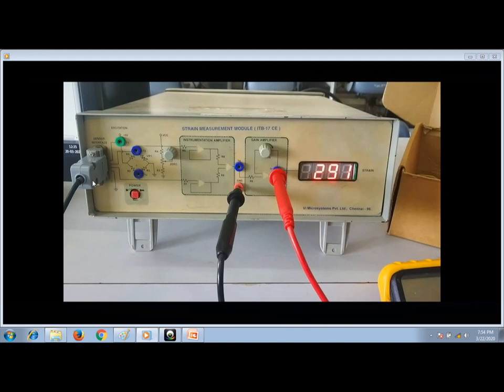The transducer is interfaced, you get the bridge output, and it is signal conditioned — that is, amplified. Across the multimeter terminals you get the electrical output in the range of 0 to 5 volts. The amplifiers are designed so that if strain is 0 you get 0 V, and if strain is at maximum (300) you get 5 V. Currently it is indicating 291 for the load of 1 kg.